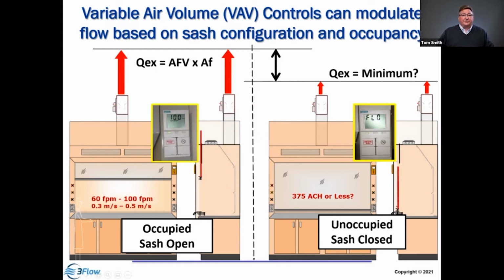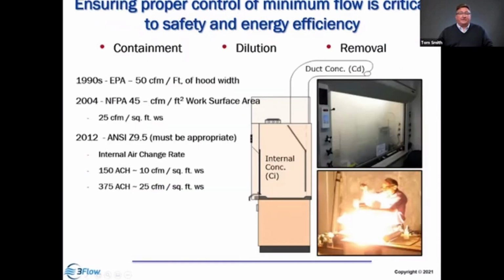If you measure 100 and it reports 100, fantastic. But what if it measured 100 and it reports 89? Is that acceptable? Does it need to be 90 to 110? What is the acceptable range? And then when you close the sash, there's no face velocity. So how do you know that it's indicating the appropriate flow? Right? So these are criteria that we need to establish before we start testing the hood to verify that it's operating properly. Now, what's at stake?